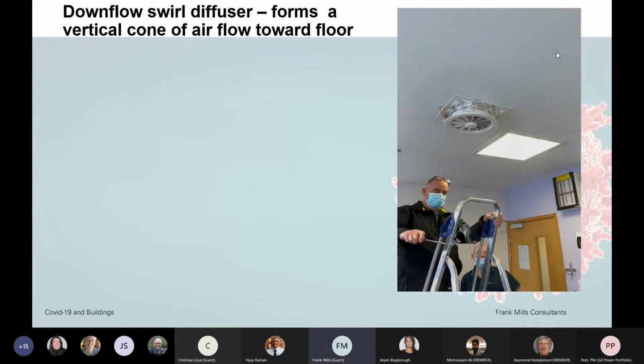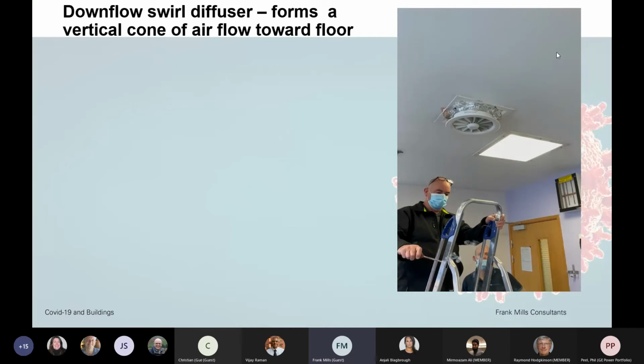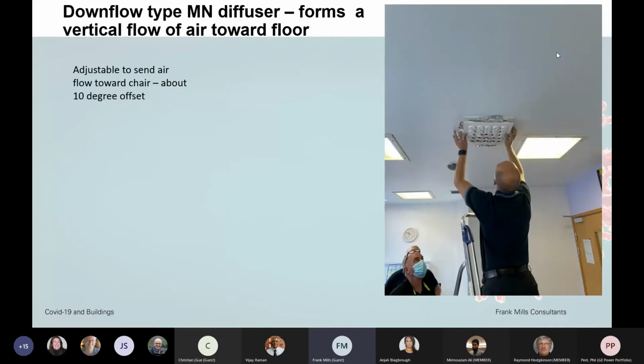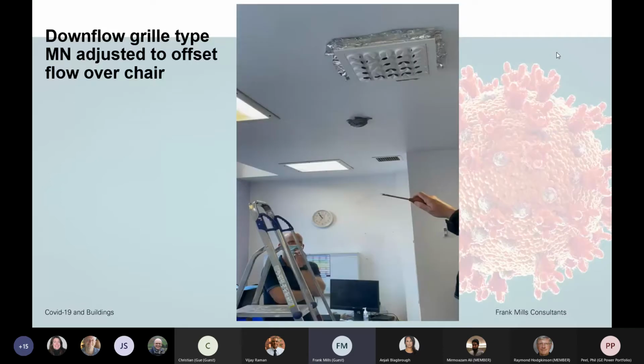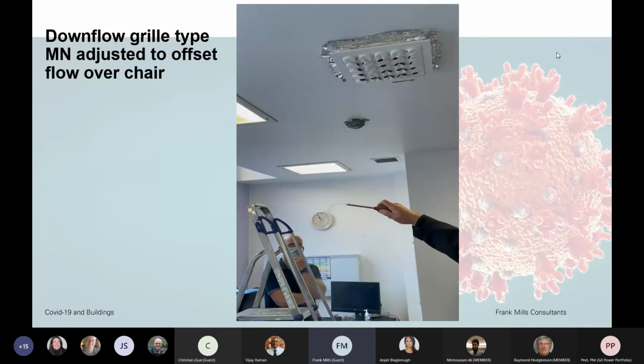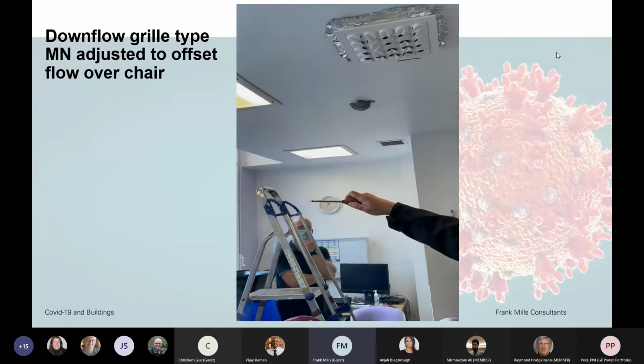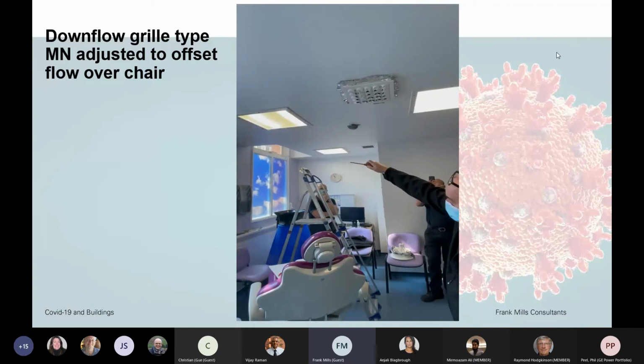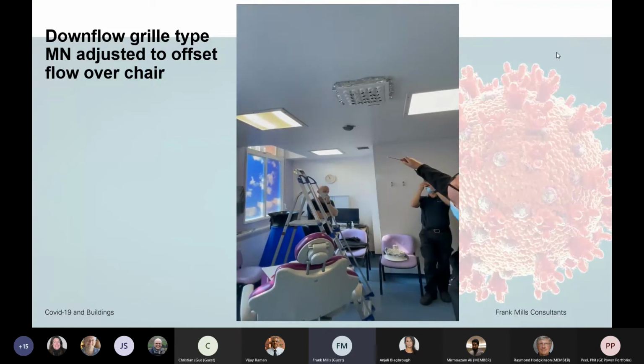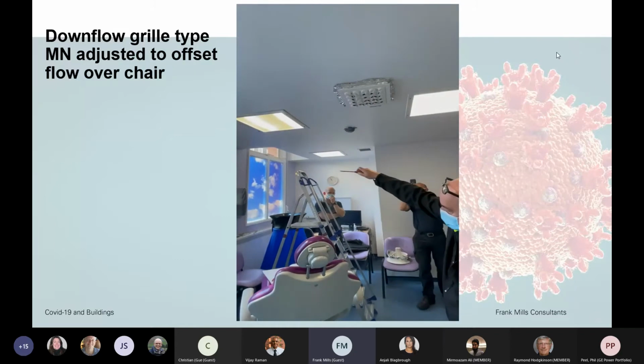So it's clean air coming down over the patient, and therefore we can protect the dentist and the nurse either side from that. And then we'd replace that with this type of diffuser, which is a nozzle jet diffuser. This has about a 10-degree offset. The reason for that is that in this particular dental surgery, the room is not square, it's not really oblong either, and the chair is not in the center. So we needed to control the air movement sideways. This is a diagram which illustrates that happening. The air is being thrown off center by about 10 degrees, which is directly over the chair, where the patient is. So it's blowing any aerosols that the patient generates downwards onto the floor.